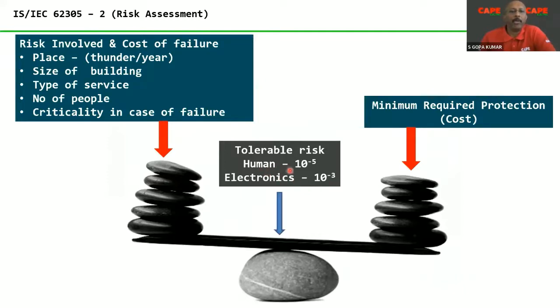For example, for human safety, 10 to the power of -5, in the sense that out of 1 lakh lightning strikes, 1 can be harmful to a human being. For protection of electronics, 10 to the power of -3 means out of 1,000 strikes, 1 can be harmful to electronics. So based on the tolerable limit on one side, and on the other side the minimum cost which has to be spent for lightning protection, we make an assessment and find out, number one, whether your building requires lightning protection or not, and number two, what level of lightning protection is required if LPS is necessary.